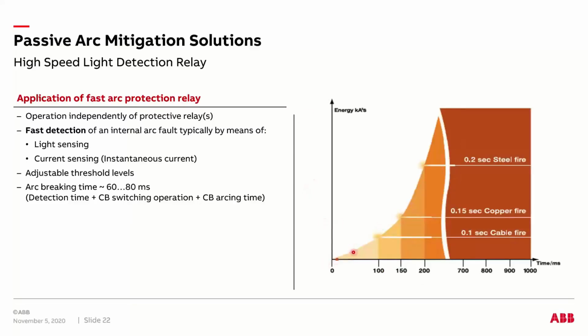So here is a nice picture that shows, right? As the time progresses, the amount of energy that is being developed inside the switchgear keeps rising exponentially. Right around 100 milliseconds is where your cable starts catching fire, and in about 150 milliseconds, the copper bus bars start catching fire, right? So you have typically less than 100 milliseconds if we have to minimize the damage within your equipment.